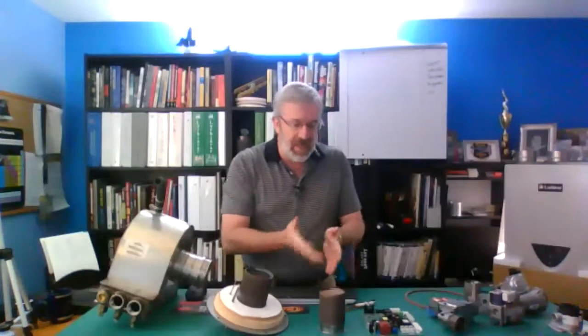It's pretty simple. Cleaning the burners, they all clean the same. They all clean with compressed air. That's it. There's no water, no brushing, no vacuuming, nothing. It's just compressed air. That's all we're going to do to clean these. Take your time, and go back and forth with that compressed air. I like to go at about a 45-degree angle, so I can push through and go out there.